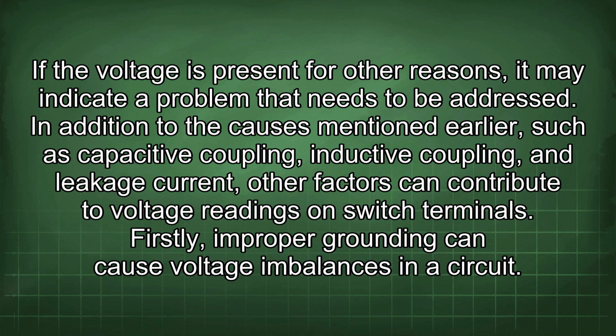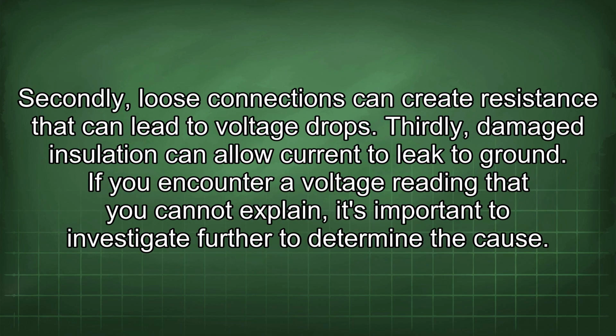In addition to the causes mentioned earlier, such as capacitive coupling, inductive coupling, and leakage current, other factors can contribute to voltage readings on switch terminals. Firstly, improper grounding can cause voltage imbalances in a circuit. Secondly, loose connections can create resistance that can lead to voltage drops. Thirdly, damaged insulation can allow current to leak to ground. If you encounter a voltage reading that you cannot explain, it's important to investigate further to determine the cause.